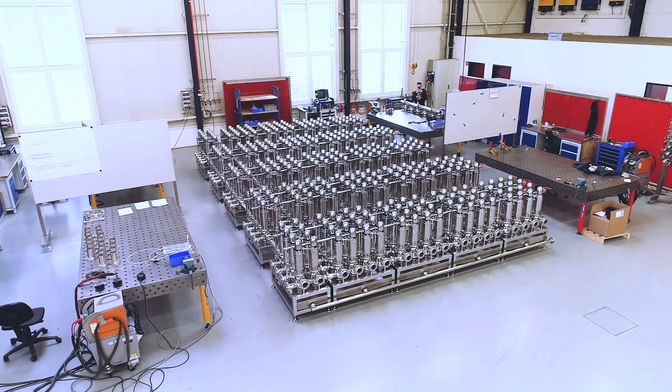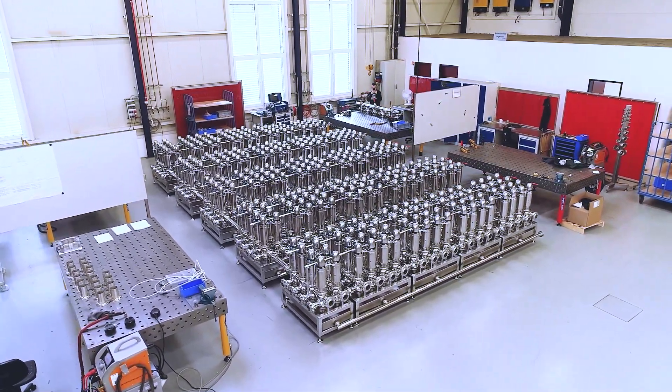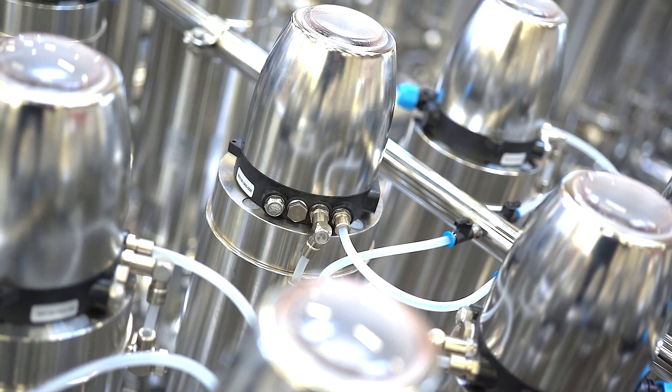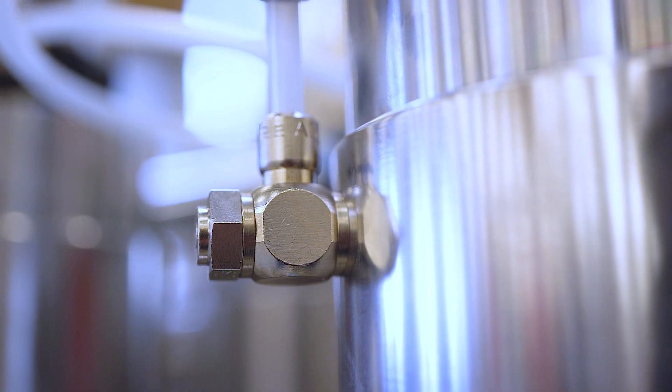On it there's 359 double seat valves — 3 inch double seat valves with K-Flex PTFE seals — and 37 butterfly valves. The control heads are intrinsically safe for a distilling area, which is a hazardous area because the fumes can be flammable, so we have to have intrinsically safe control heads with solenoids in the head.